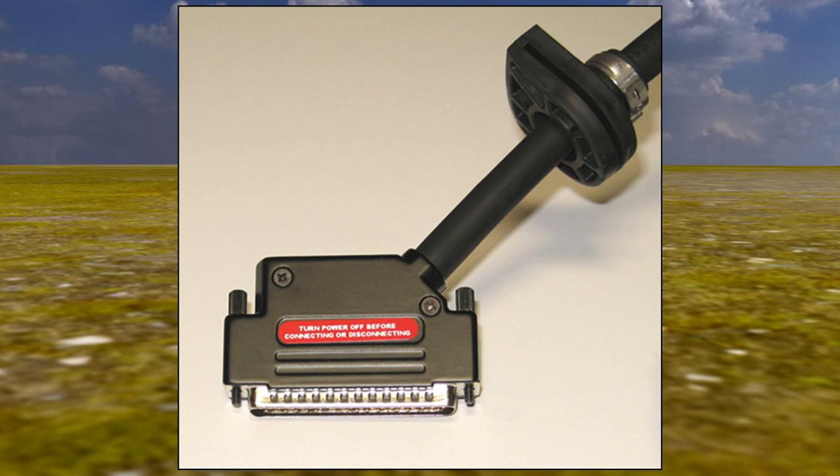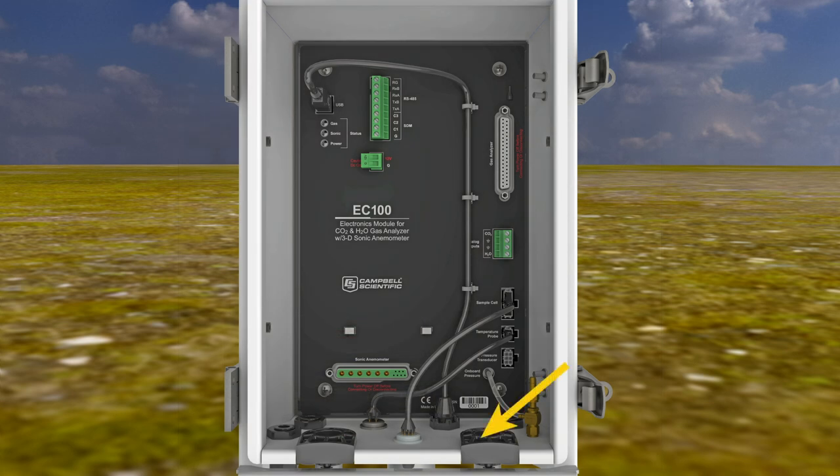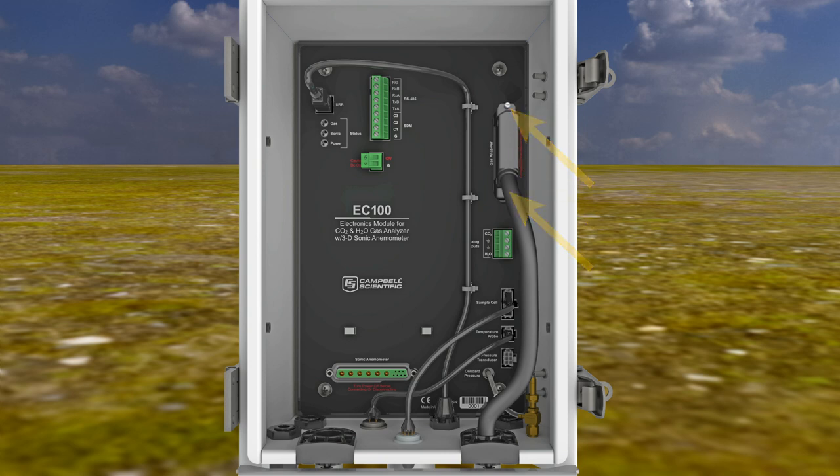Locate the thicker black cable coming from the IRGASON — this is the gas analyzer umbilical cable. Remove the black rubber plug from the gas analyzer port on the bottom of the EC100 enclosure and store the plug in the mesh pocket inside the enclosure. Slide the connector on the gas analyzer cable through the open port on the EC100 enclosure and plug the connector into the EC100. Secure the connector with the thumb screws. Repeat this process for the IRGASON sonic anemometer cable: remove the rubber plug from the sonic anemometer port, slide the cable through the port opening, plug the connector into the EC100, and secure the connector with the thumb screws.